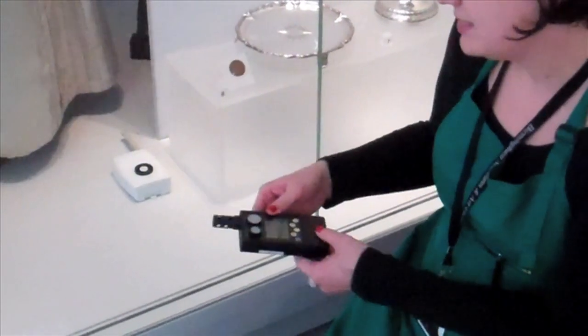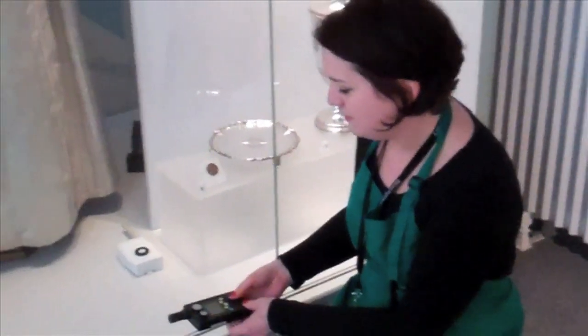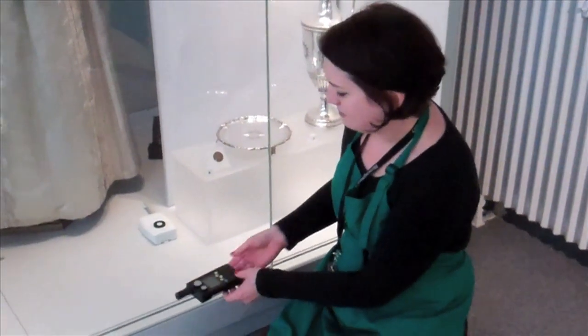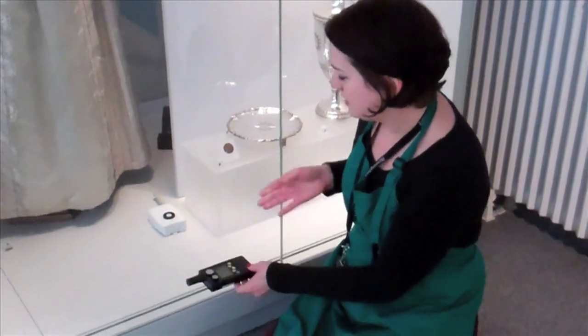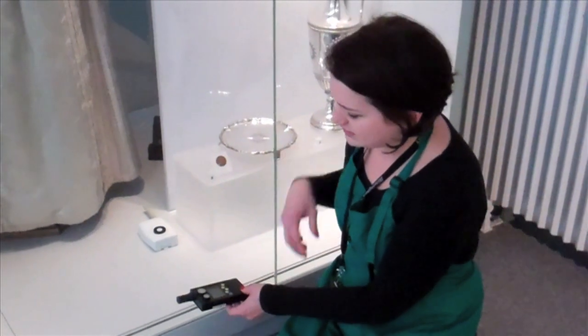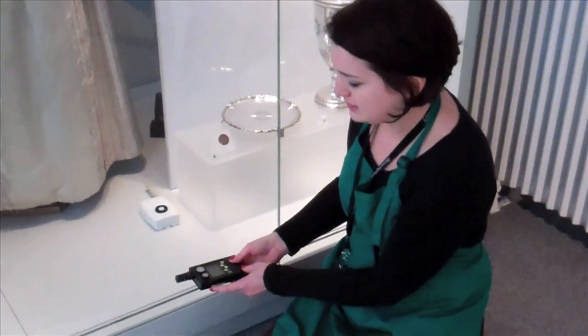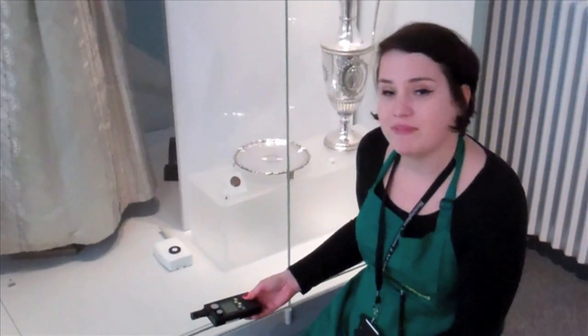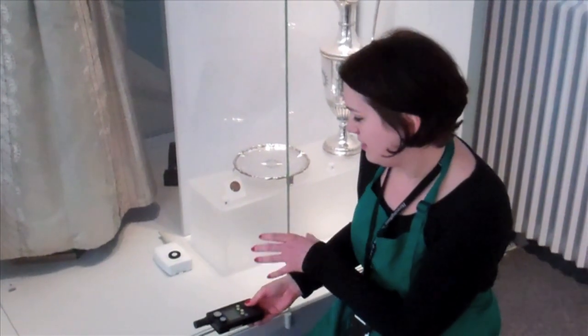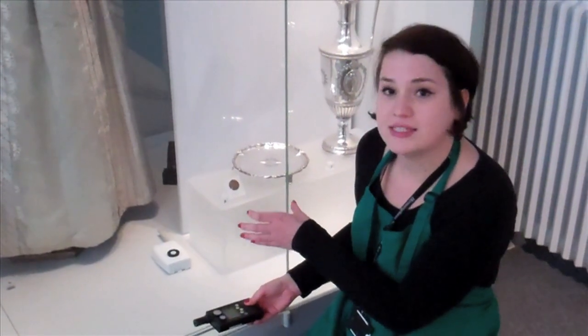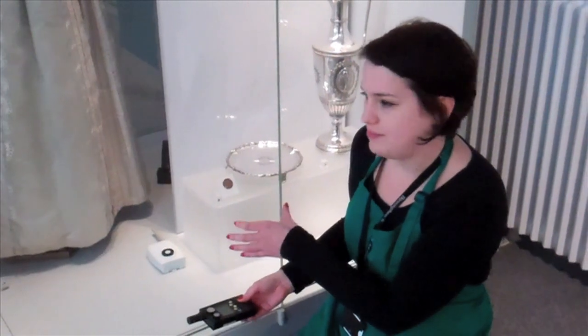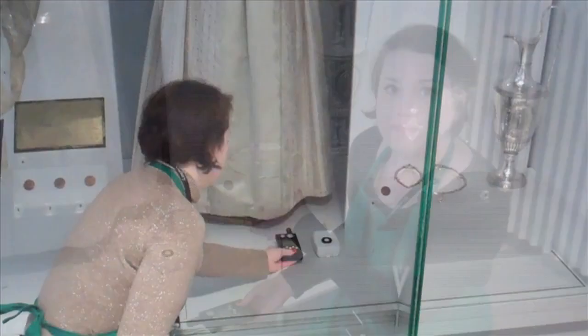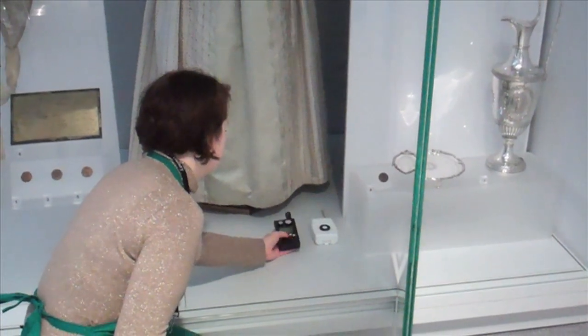And we can see from this that holding the device close to the one in the display case that UV is zero around here. So we'll be expecting that the device which is in the display case is not set properly. It should say zero UV.